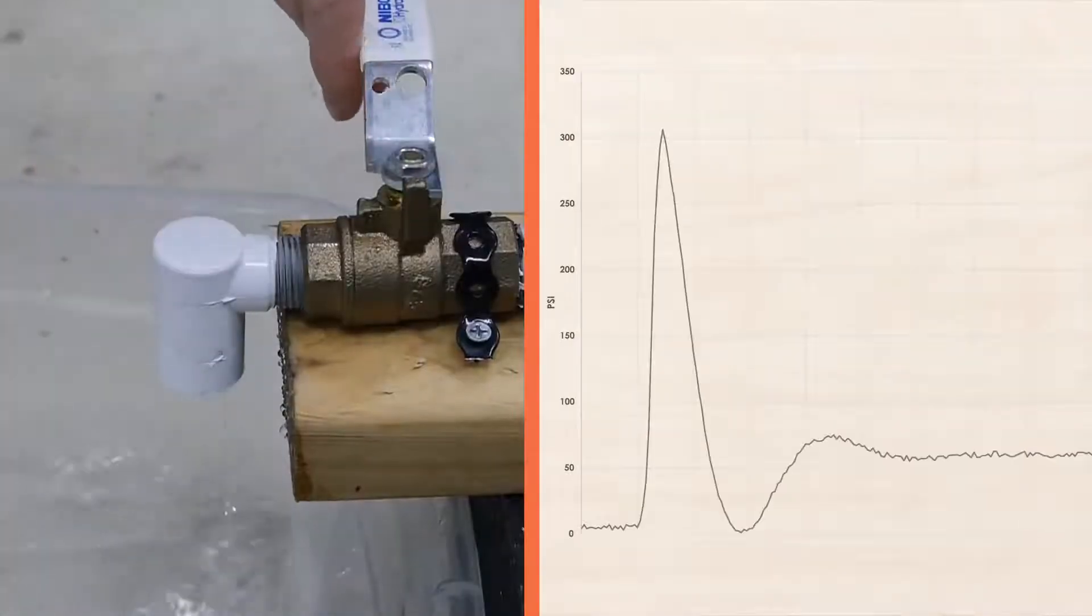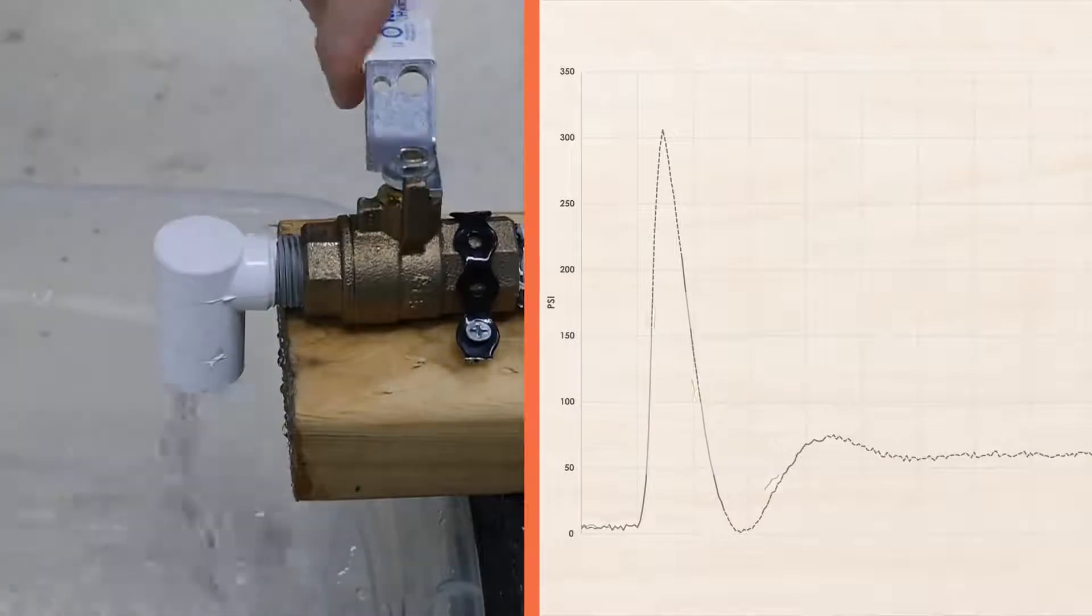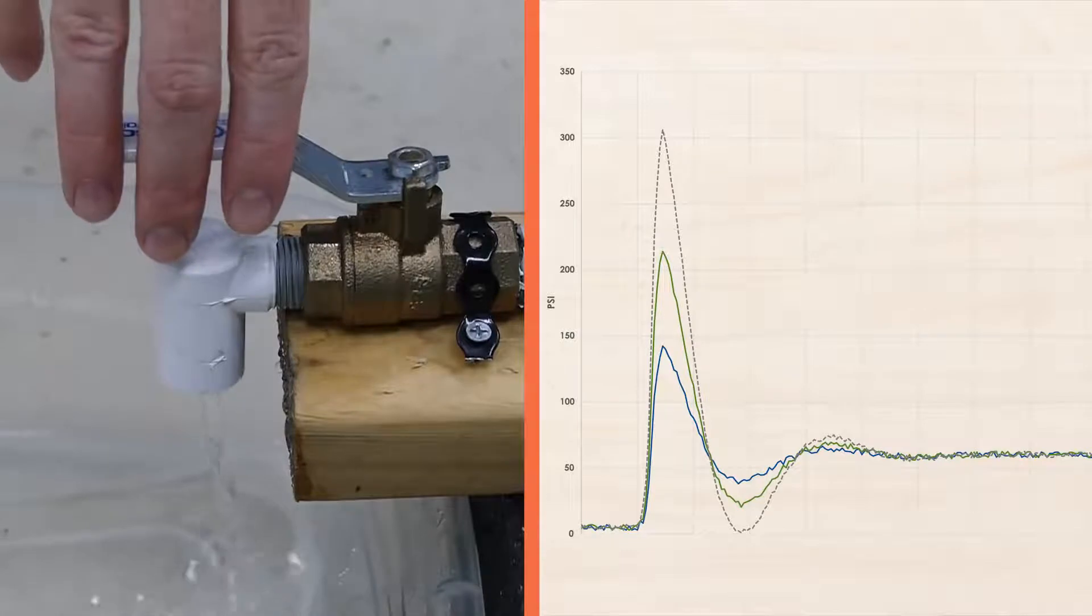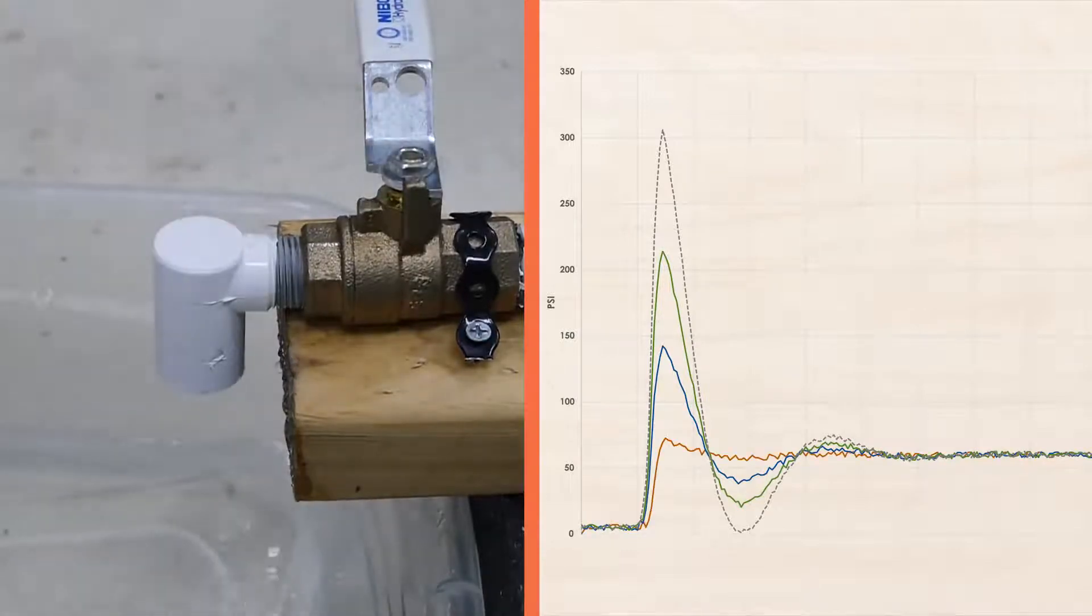In this case, my pipe size is fixed, but I can reduce the flow rate to limit the velocity. Each time I reduce the velocity and close the valve, the resulting spike in pressure decreases.